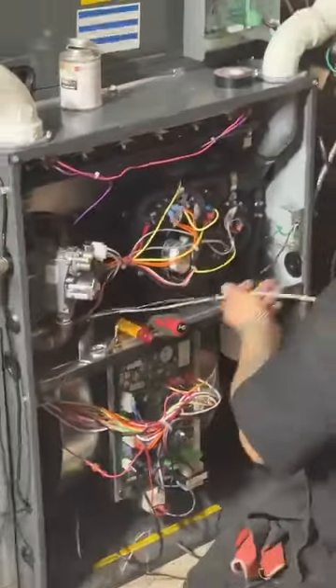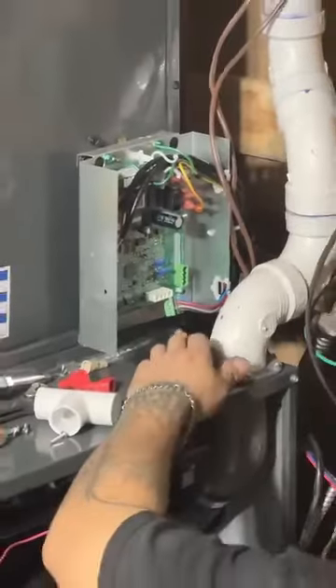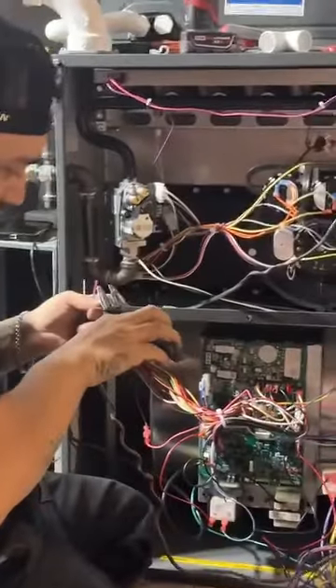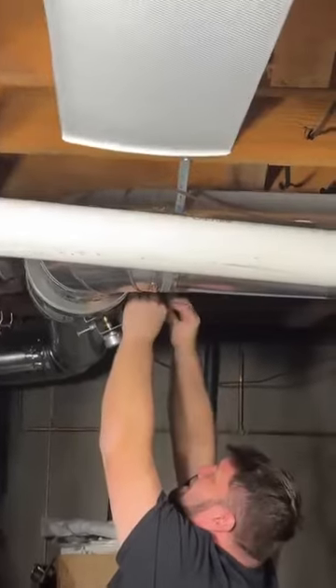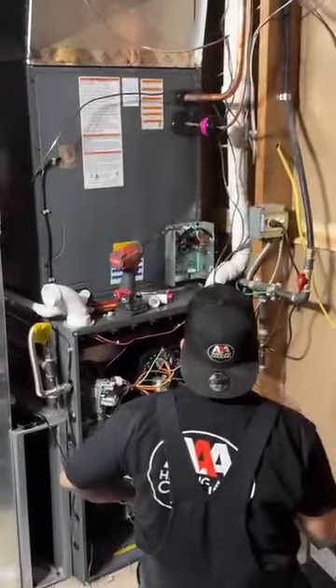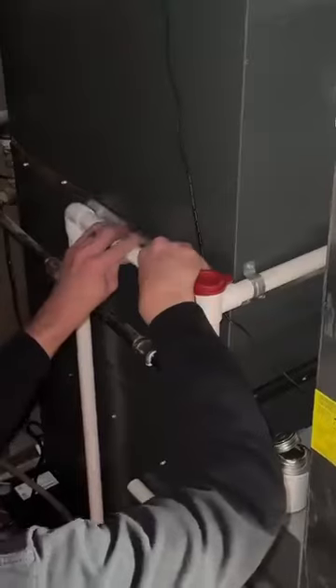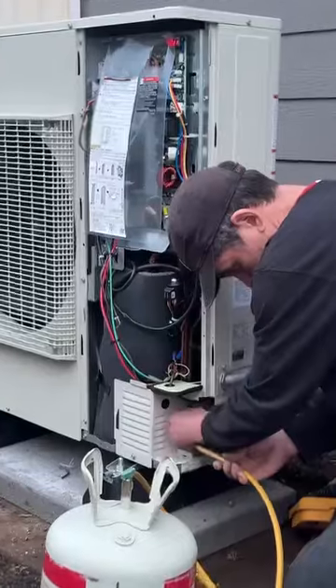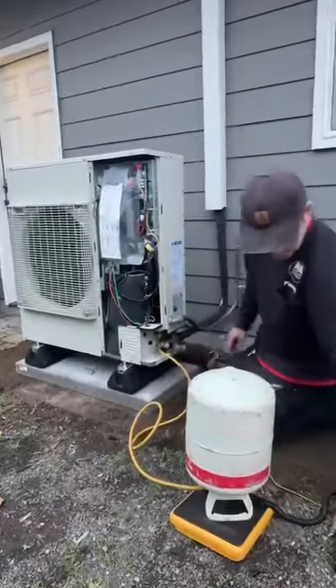Now we begin wiring in all the high voltage and then switch gears to the low voltage equipment, which is run into the transformer seen here. This lets it power and communicate with the board. This customer had a damper on their previous setup, so we had to wire that in too during this step. After that, we install a new condensate pump and easy trap for this setup. Back outside, we add refrigerant to the new system due to increased line set length.